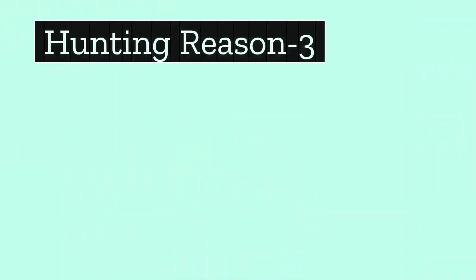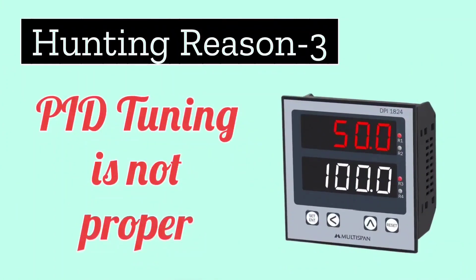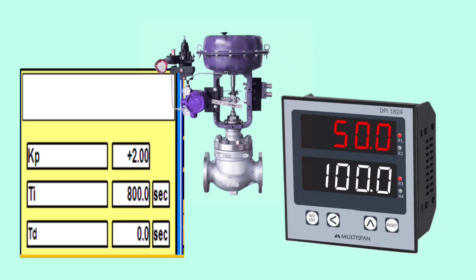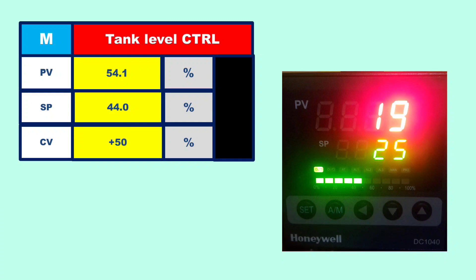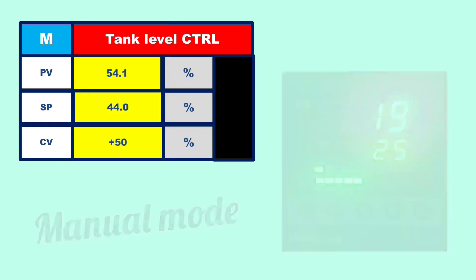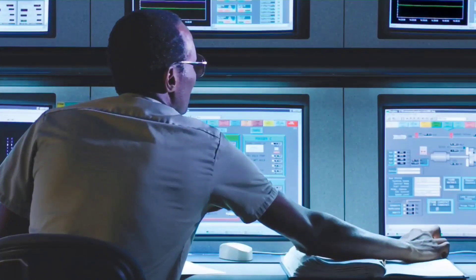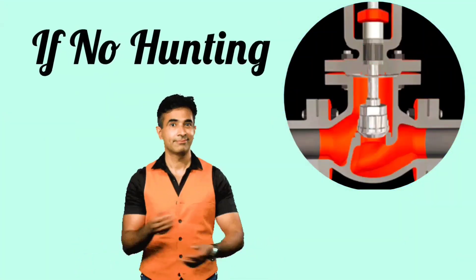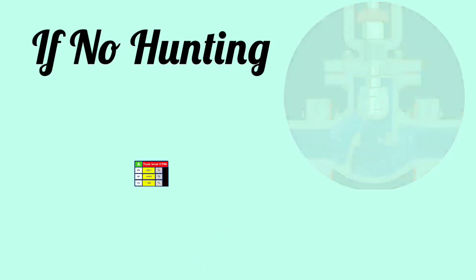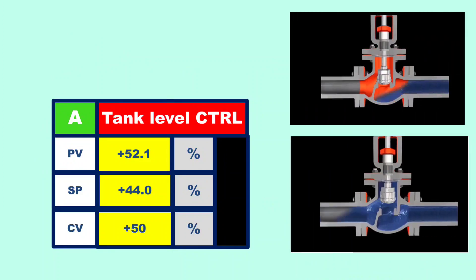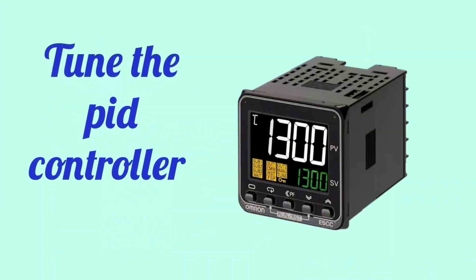The third reason for hunting may be that PID tuning is not proper. Due to improper tuning of the PID controller, the problem of control valve hunting can also arise. To check this, operate the PID controller in manual mode at different outputs and operate the control valve. If there is no hunting in manual mode, then operate the valve from the PID controller in auto mode. If hunting occurs in auto mode, do the tuning of the PID controller.